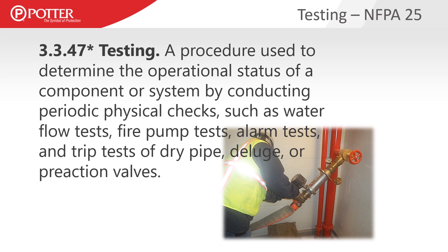For example, if you do the annual flow test on a fire pump this year, it tells you certain data points. But the value in that test comes from comparing it to previous tests — that gives you an indication of a problem more so than just the data you collect during that particular test.